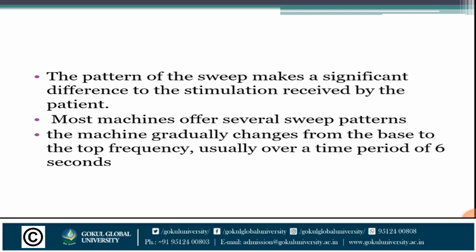Most machines offer several sweep patterns. With a constant signal the nerve will accommodate, and a sweep is often used to overcome this problem. The sweep should be appropriate to the desired physiological effect. The mode of delivery of the selected sweep varies with the machine. Most commonly, the machine gradually changes from the base to the top frequency, usually over a time period of 6 seconds.